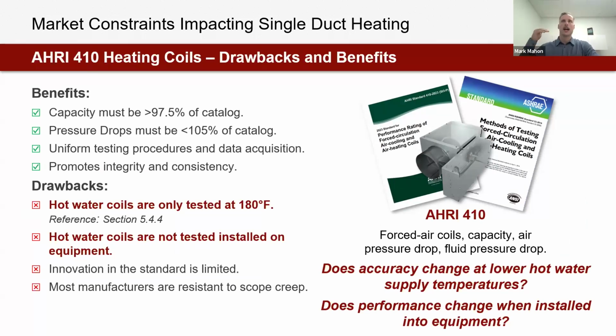It makes sure that manufacturers have accurate performance. So when we look at a product that's certified to this standard and audited to this standard, capacity needs to be at least 97.5% of what we say it will be in our catalog. And they're going to audit and check this every single year. Pressure drops, whether that's air side or water side, must be less than 105% of catalog. They will audit and test that every year. They also create and constrain the way that we test and the way that we acquire data. So there's minimum viable data acquisition and testing procedures, and it makes sure that manufacturers have integrity and consistency. But this standard is large and it's complicated.